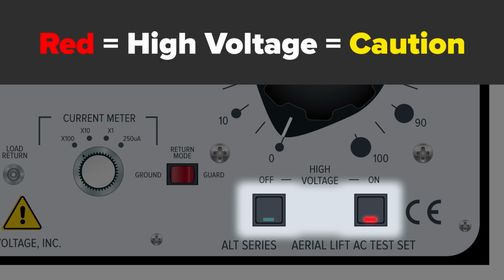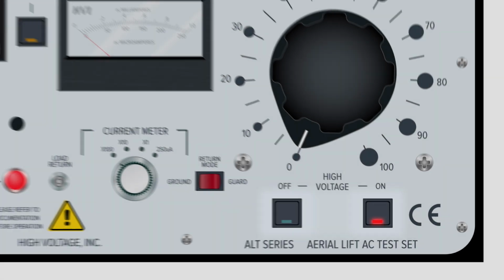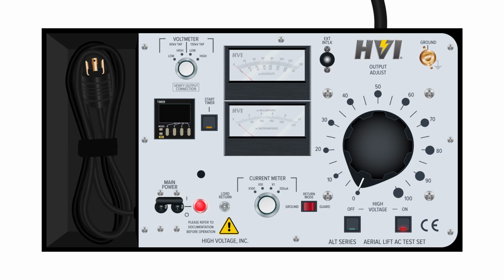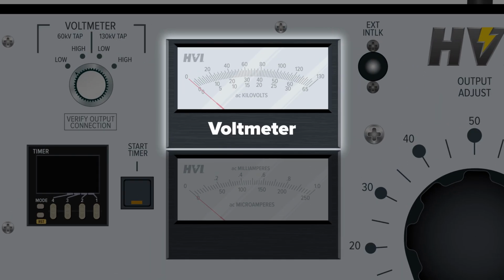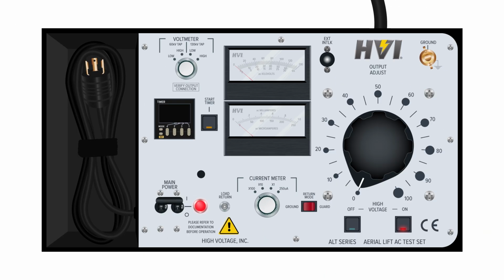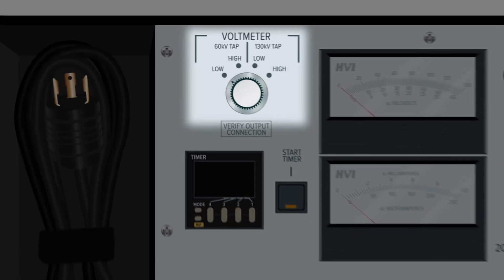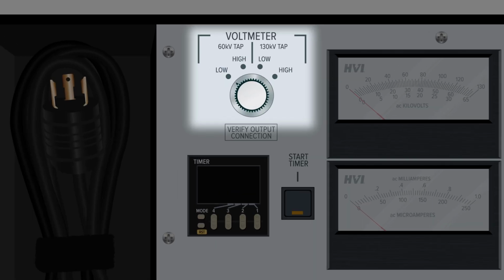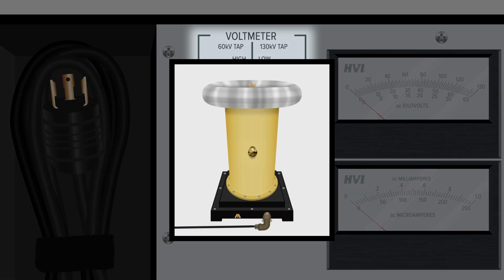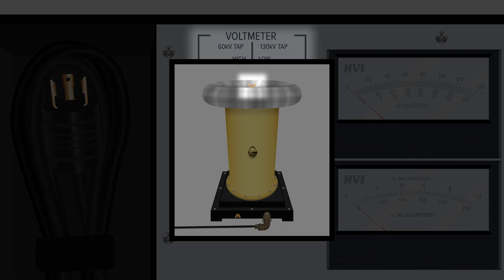in red, meaning caution. The ALT series Hipots have two main meter displays, a voltmeter and a current meter, each with their own range switch. The voltmeter is located in the top of the panel. When the high voltage circuit is energized and activated, it displays the voltage level. The meter has three display ranges, which are controlled by the voltmeter range switch, directly to the left of the voltmeter.